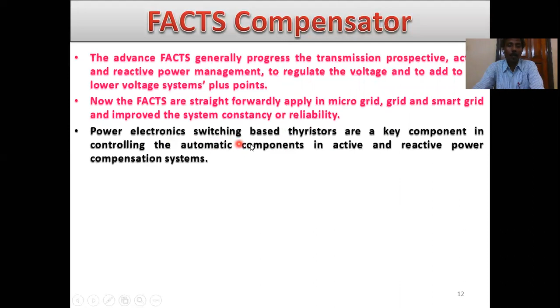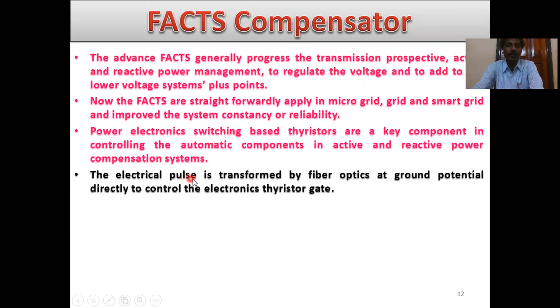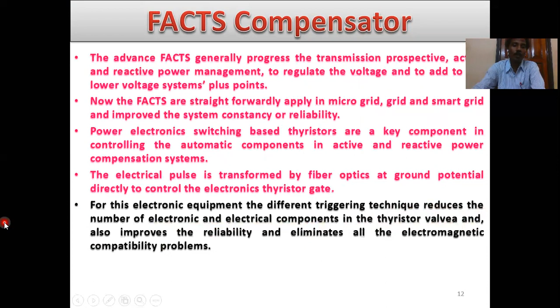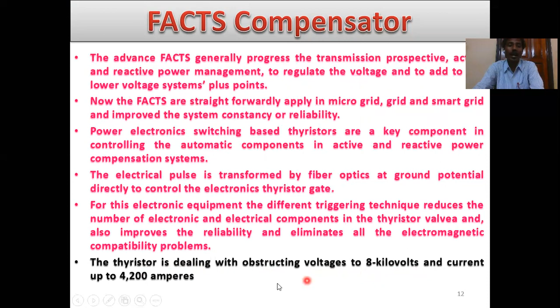Power electronics switching based thyristors are a key component in controlling the automatic components in active and reactive power compensation systems. The electric pulse is transmitted by fiber optics at ground potential directly to control the electronic thyristor gate. For this electronic equipment, the different triggering technique reduces the number of electronic and electrical components in the thyristor valve, improves the reliability, and eliminates all the electromagnetic compatibility problems. The thyristor is dealing with blocking voltage up to 8 kilovolts and current up to 4,200 amperes. So, thank you.